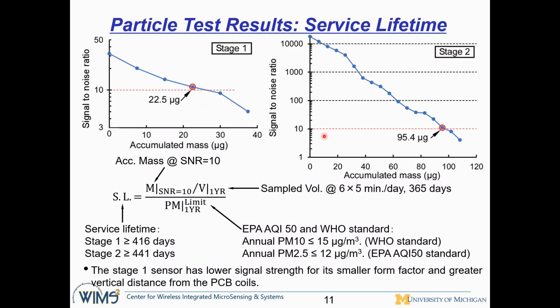These two plots show the sensor accumulated mass evaluation for the stage 1 and stage 2 sensors. The x-axis is the accumulated mass, and the y-axis is the signal to noise ratio, or SNR. The left plot shows the accumulated mass when the SNR is approximately equal to 10, and that is 22.5 microgram for the stage 1 sensor. The right plot is for stage 2, and when the SNR is approximately equal to 10, the accumulated mass is 95.4 microgram for the stage 2 sensor.